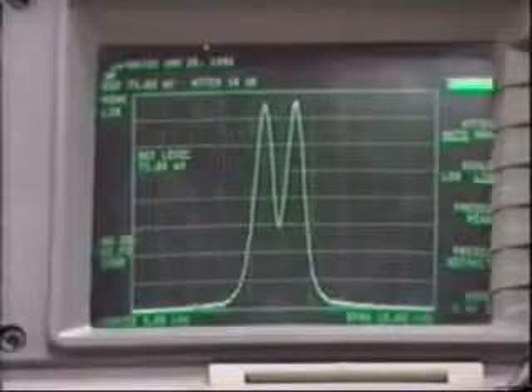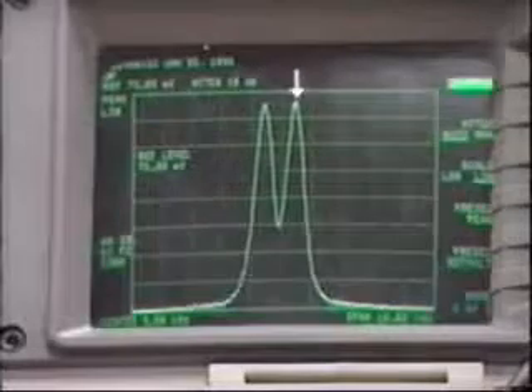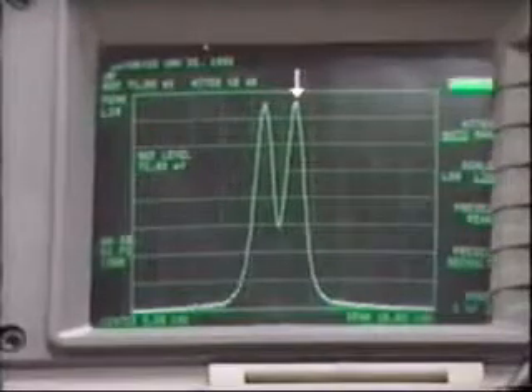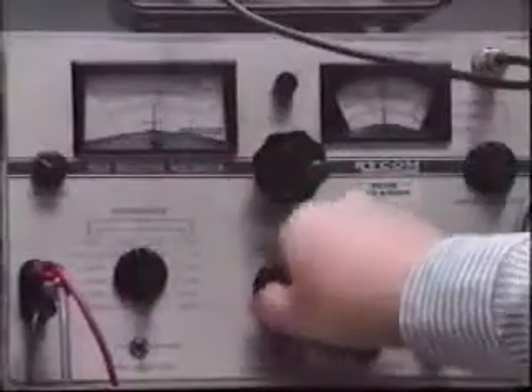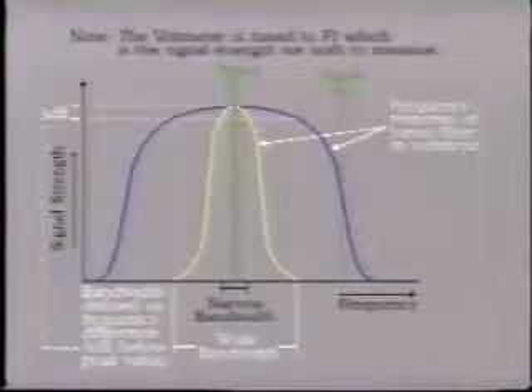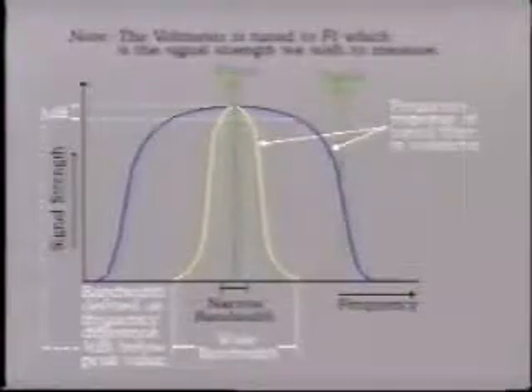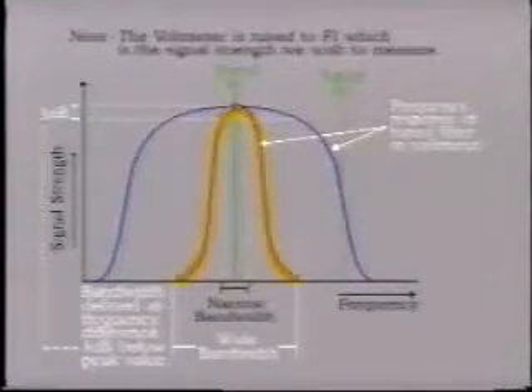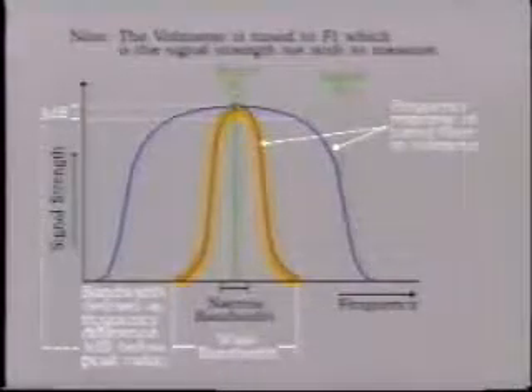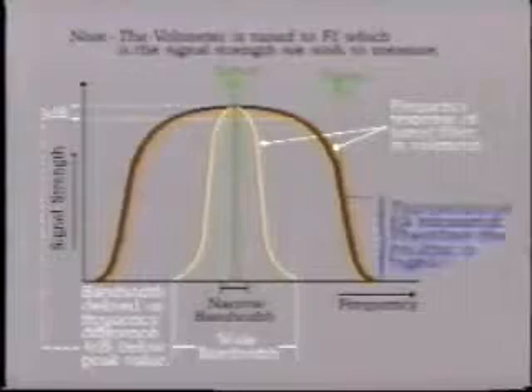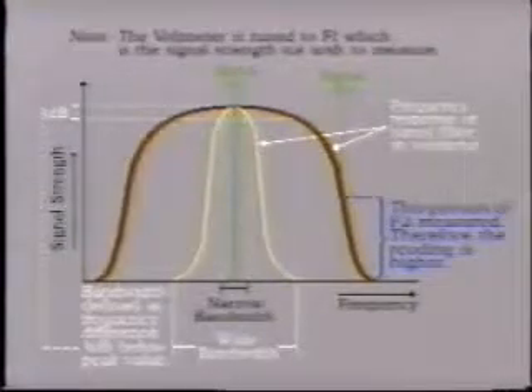In this example, we have two signals, one at 9 kilohertz and the other at 10 kilohertz. This is the reading of the 9 kilohertz signal when a narrow bandwidth is selected. When we increase the bandwidth, the measured signal strength increases considerably due to influence from the second frequency. The bandwidth must be chosen so as to prevent energy from adjacent signals causing a measuring error. With the narrow bandwidth selected, we measure the signal strength in dBs of just the 9 kilohertz signal. On the wide bandwidth setting, we get a higher dB reading.